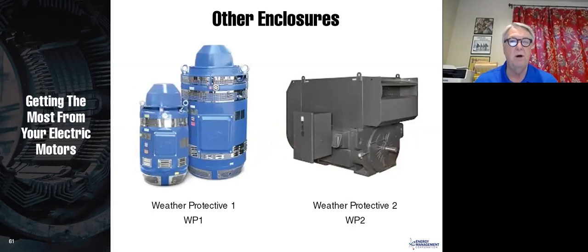This is weather protective 1 on the left and weather protective 2 on the right. Weather protective 2, the air has to actually make 3 90-degree or greater turns, and that helps get some of the particulate out. And it has an area inside the motor where you have a low air velocity. So what you're trying to do, this is an open motor. It's very difficult in very, very large motors sometimes to cool it. And so you may need to have an open motor in order to get proper cooling. And a WP2 gives you better protection from environmental particulate than a WP1, which does not have those 3 90-degree turns.